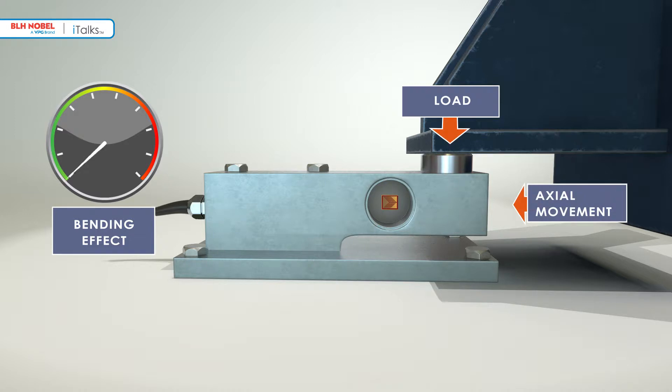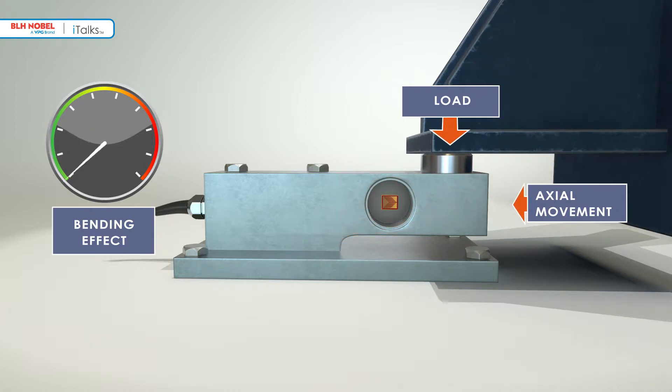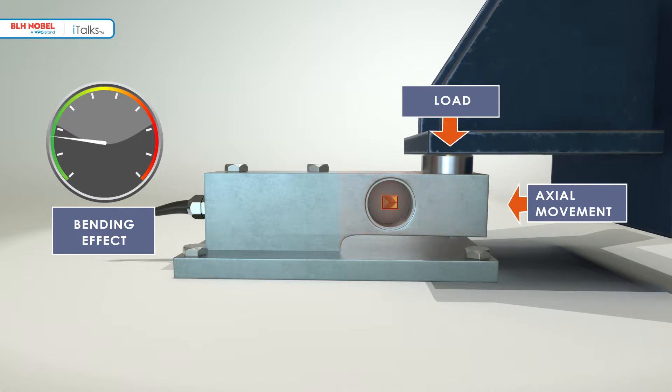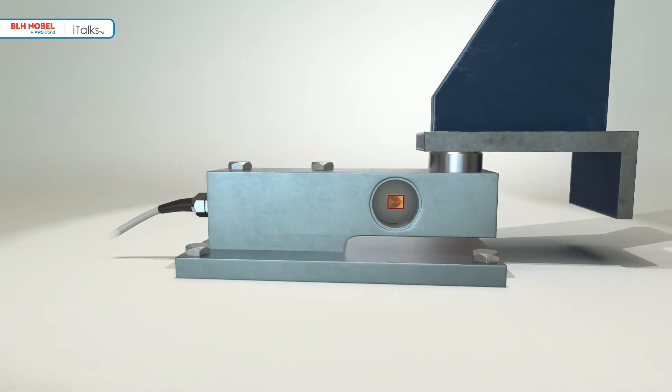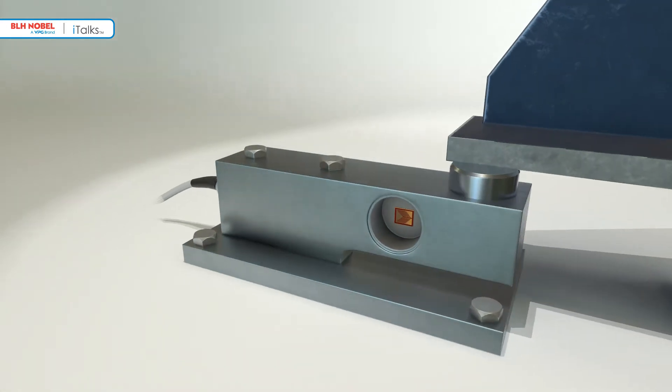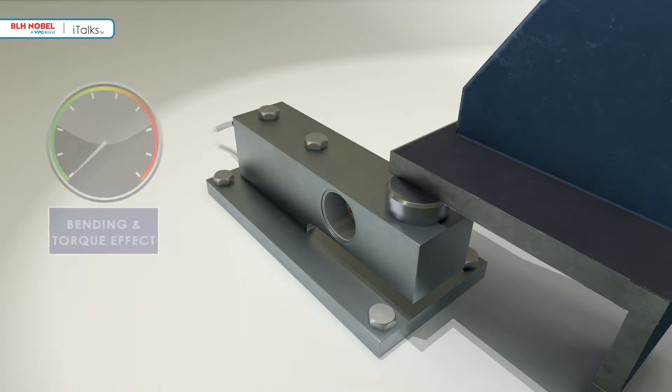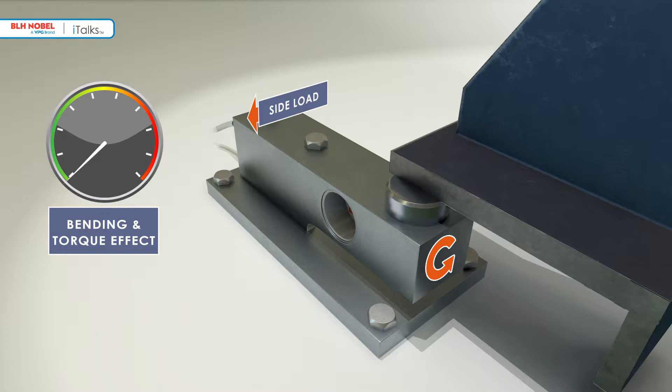In a real process weighing application, however, the bending effects can change unpredictably due to thermal or structural movement. These additional strains result in measurement errors. The side loads can be in any direction, caused by agitation, wind loads, or the flexing of structural supports and piping connections. In addition to bending errors, the load cell is now subject to twisting forces, which result in additional torque errors.